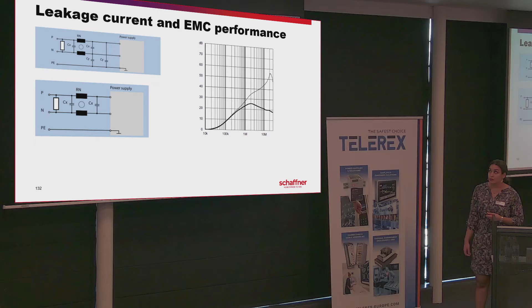So there are a lot of filters that we have. They definitely don't have common mode capacitors to be able to comply to the medical standard, but they have an earth choke, and this is how we can enhance the filter performance without impacting the leakage current.